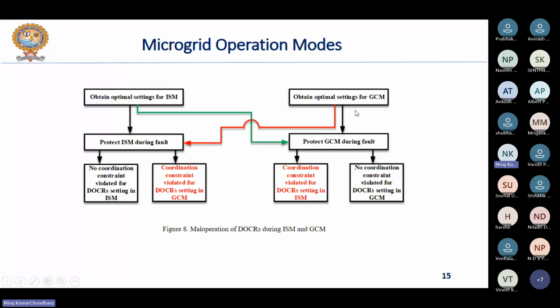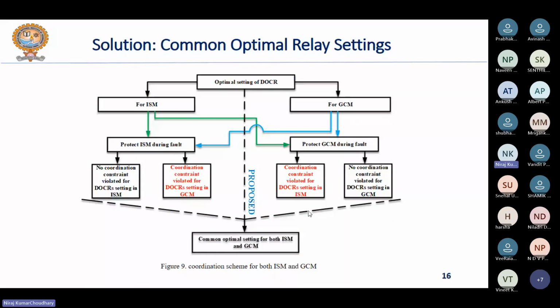So the same problem has been observed that when you have calculated the settings of relays, that is your time multiplier setting or current setting of the relay, then that will be valid for the grid connected mode of operation only. If you put the settings obtained in the grid connected mode into the islanded mode of operation, then again there will be some constraint violations. So the solution is that you need to combine the different constraints of grid connected mode and islanded mode, and accordingly you need to calculate the common optimal settings that should be valid for both grid connected mode of operation and islanded mode of operation of the microgrid.